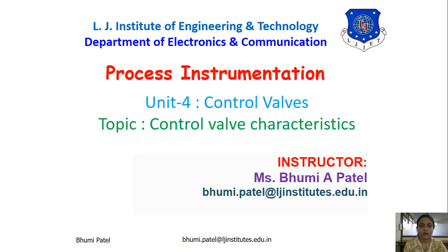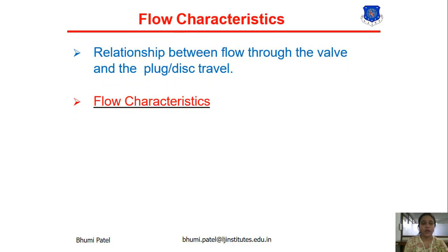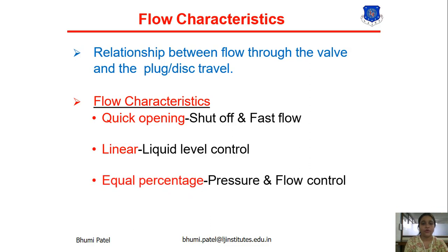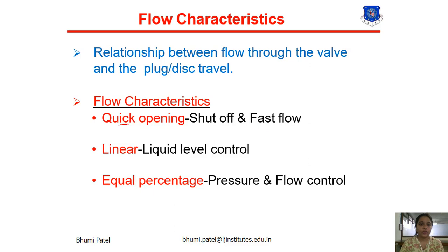Today we will study about the control valve characteristics. In the last session, we studied about the flow characteristics. The flow characteristic is the relationship between flow through the valve and the plug travel. We have basically three types: quick opening, used for on-off and fast flow; linear, used for liquid level control; and equal percentage, used for pressure and flow control.